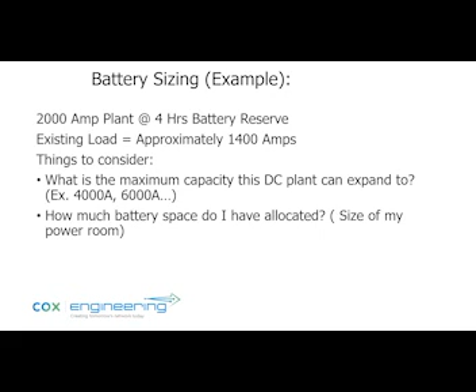The larger ones are 10 to more like 15 years these days. So you need to have enough floor space to put as many batteries as you're going to need for the ultimate size of the DC plant in the room. So you have to look at the low voltage cutoff of the equipment, and each of the equipment manufacturers is going to have a threshold.